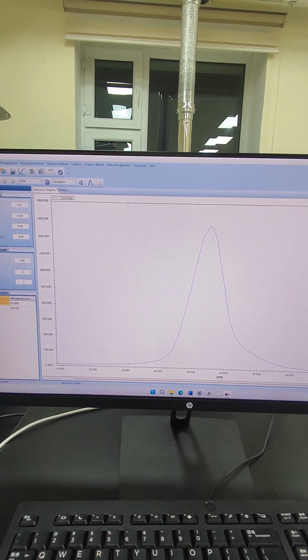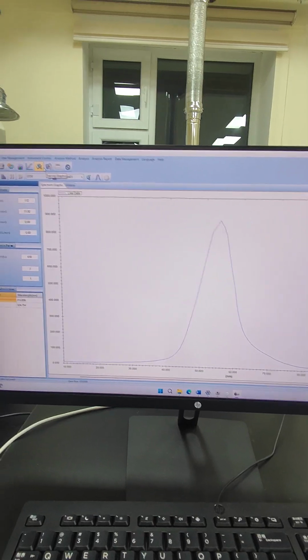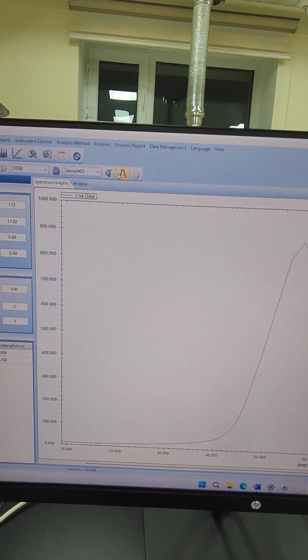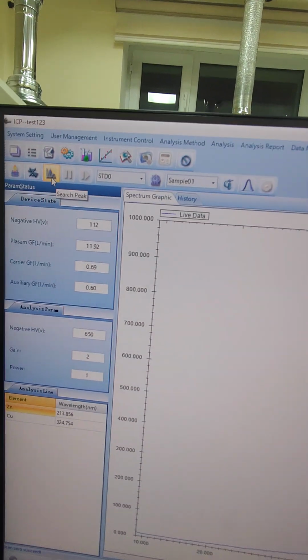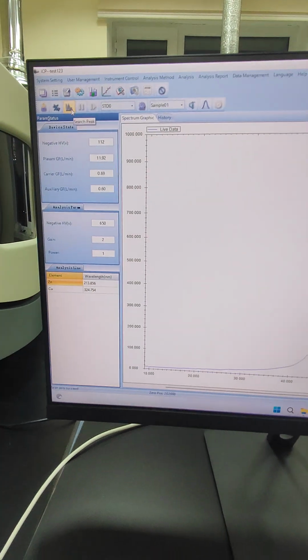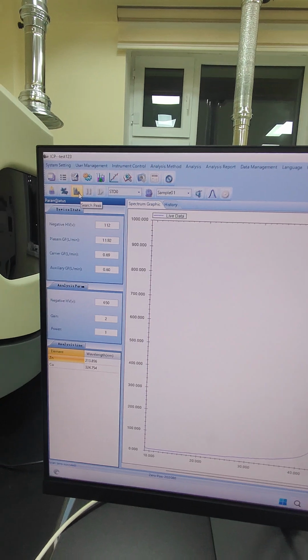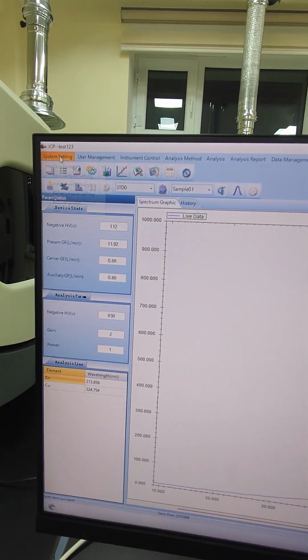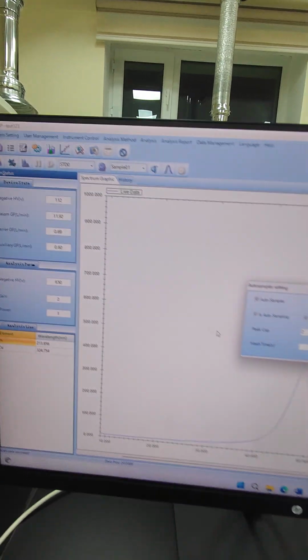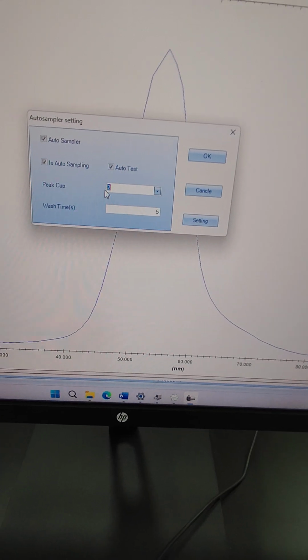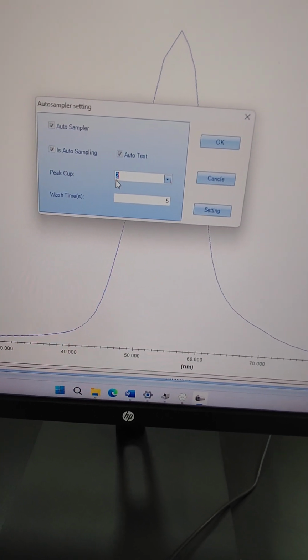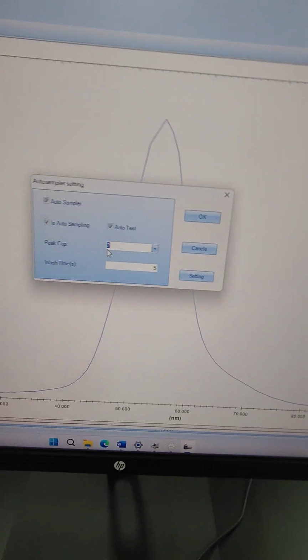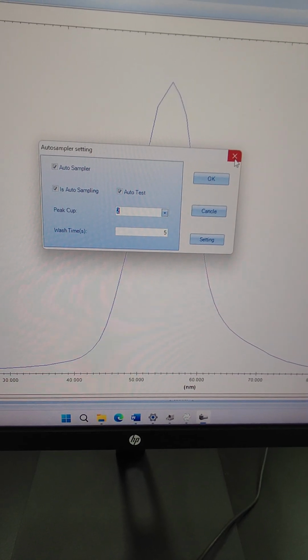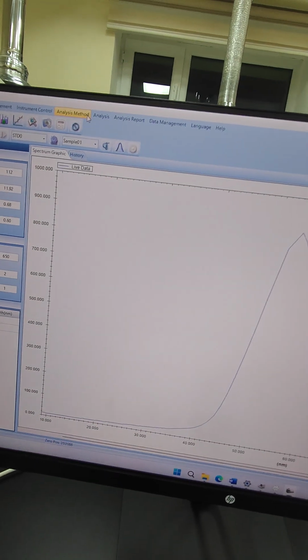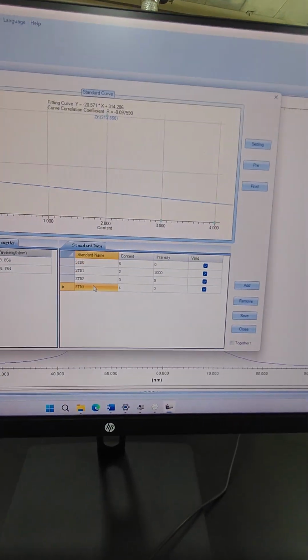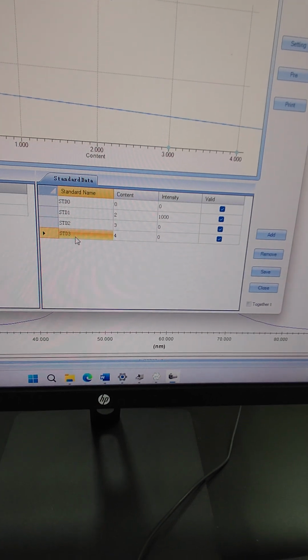And next we need to go for the search peak. Actually, before we go to search peak, we need to set the auto sampler setting, the peak cup position. The peak cup position we usually set to the biggest concentration position. For example, the biggest concentration content is standard 3.